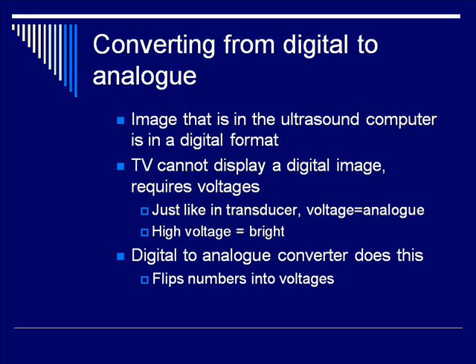The scan converter can also take us back from digital to analog. Why would we want to do this after spending so much time getting the signal into digital? Well, many ultrasound machines — especially older machines — use a display that's a television screen. Television doesn't actually display a digital image; it requires voltages, which is an analog signal. So we have a digital-to-analog converter that flips those numbers back into voltages for use in display.